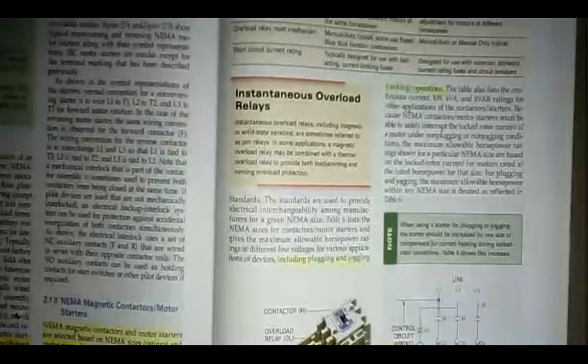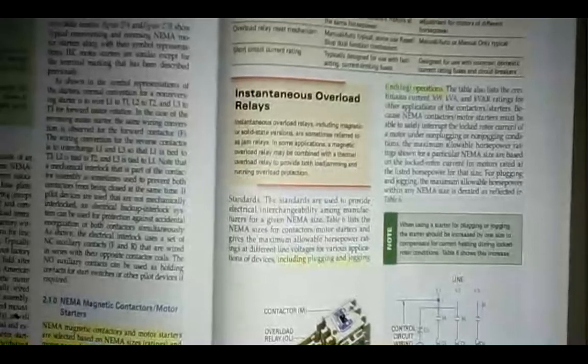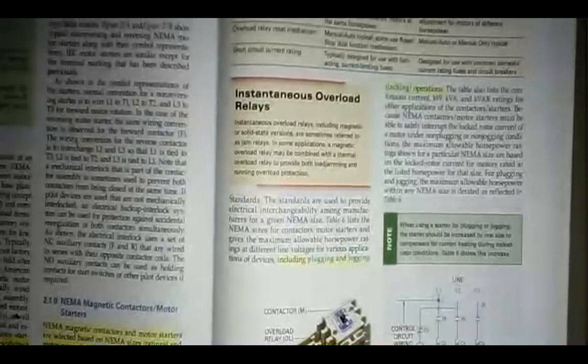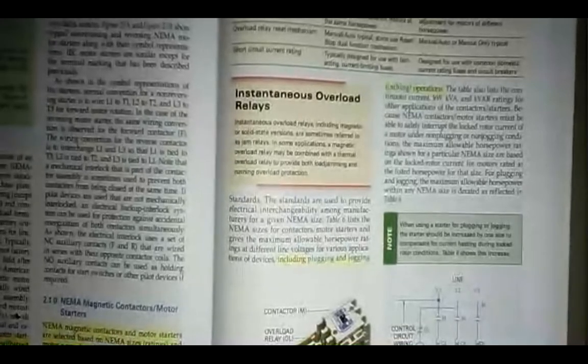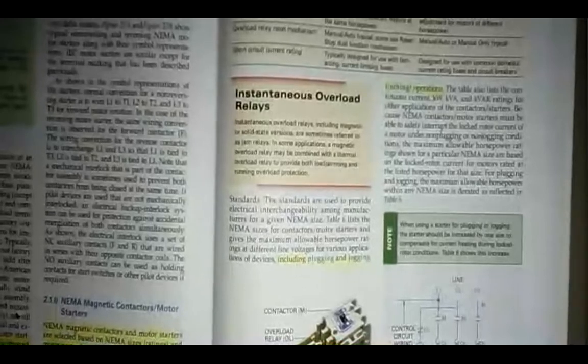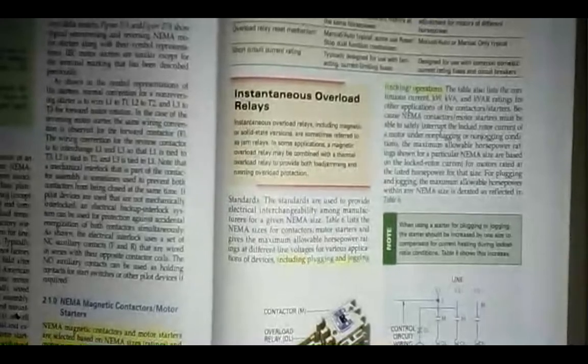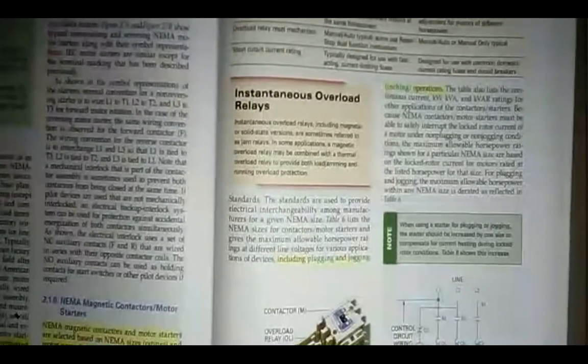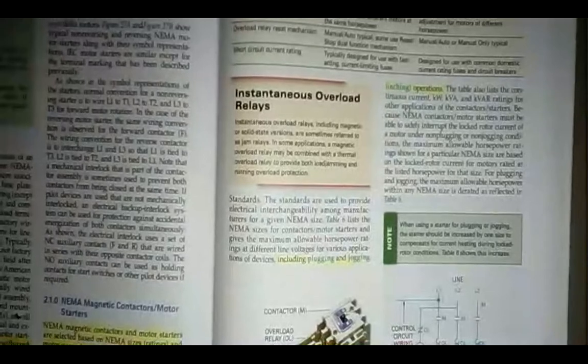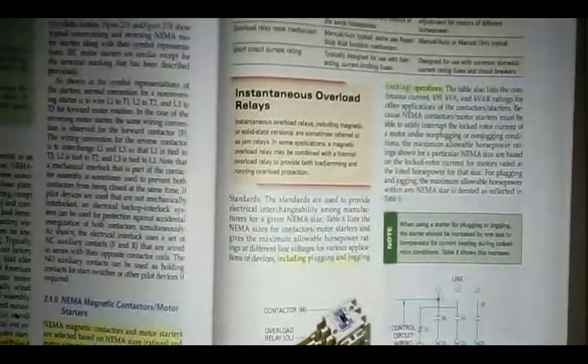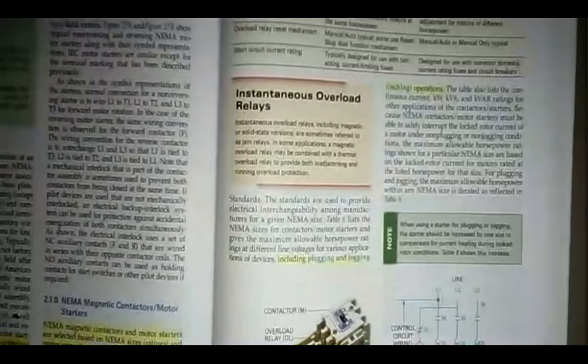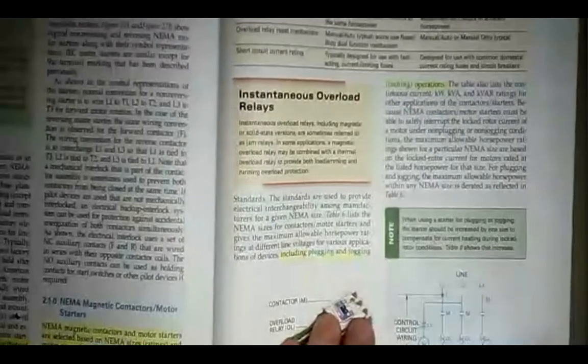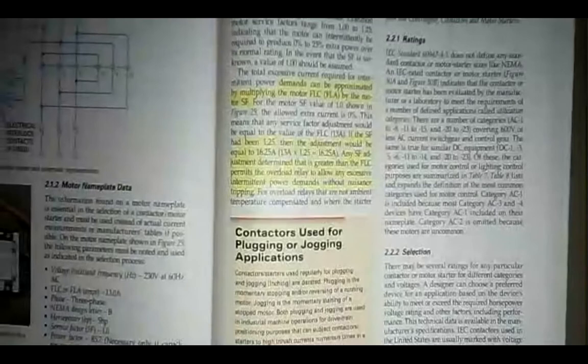Mr. Young, does that mean lightly pressing the button? Well, pressing it and letting go quickly and not allowing the maintain contacts to energize. We'll see what the maintain contacts are later, but we don't want them to seal in because then the motor would just be running. But we bump it with the maintain contact open, and we bump the motor and it'll just move that conveyor a little bit. So jogging and inching are the same thing.